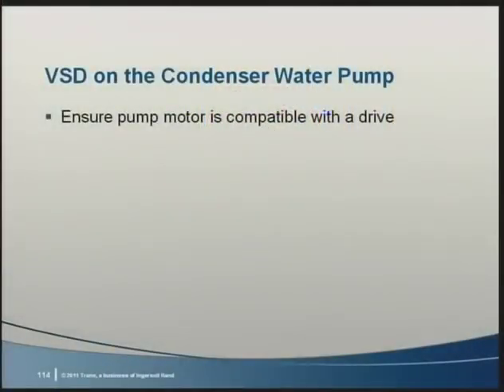There sure is, Susanna. The final retrofit opportunity we'll discuss today is putting a variable speed drive on the condenser water pump. We discussed this in a 2006 E&L on variable speed drives, but this subject comes up a lot, so we wanted to address it specifically with respect to retrofits. First, you need to make sure that the pump motor is compatible with a variable speed drive. If not, you can't just slap a drive on it or you'll have issues.